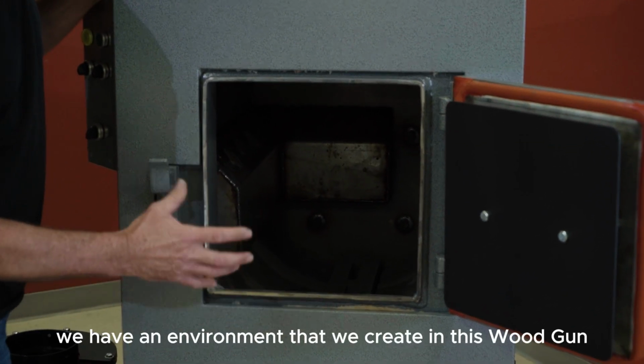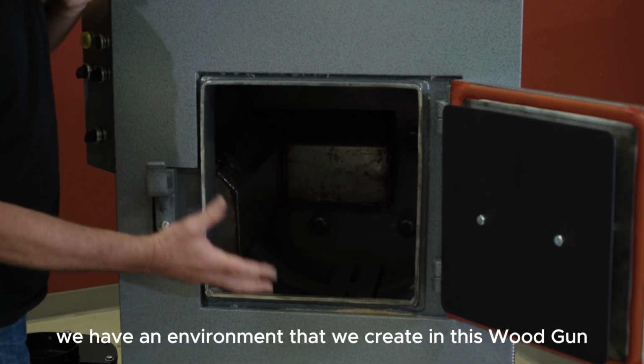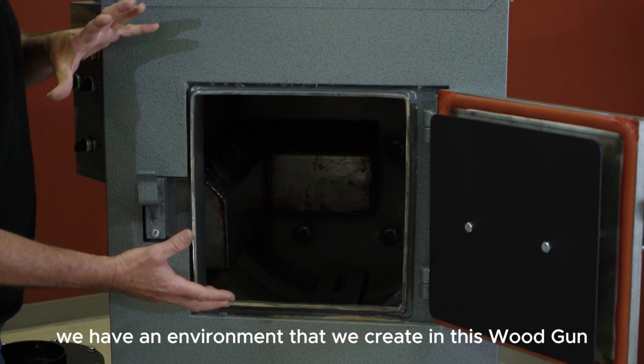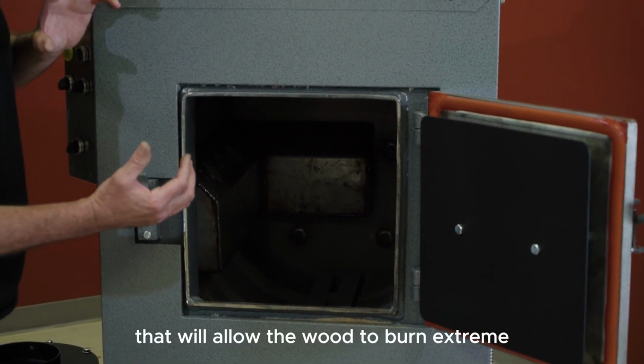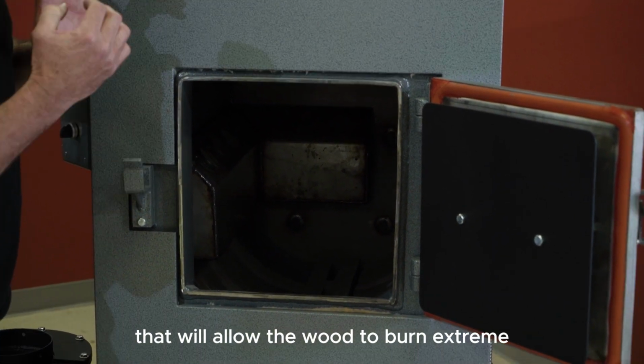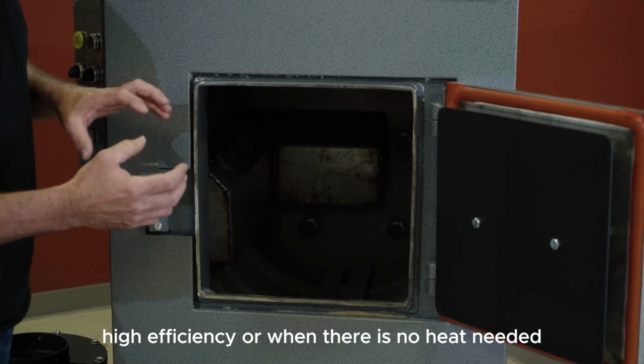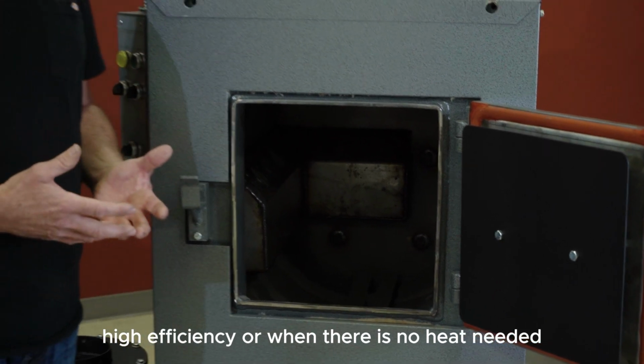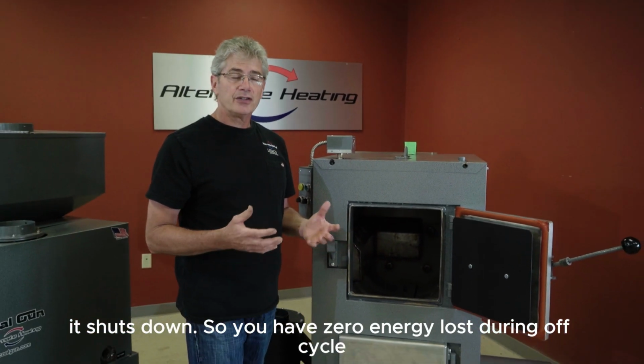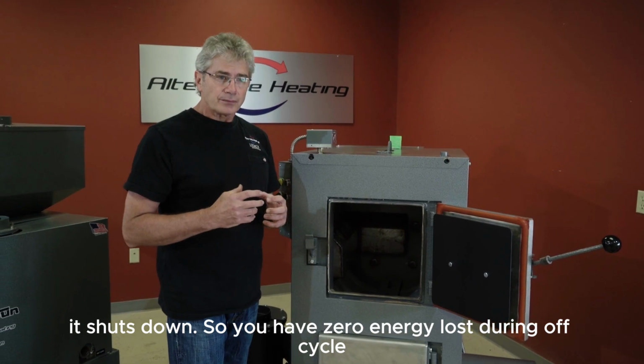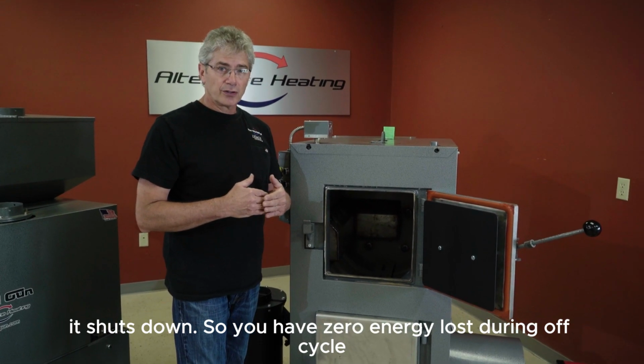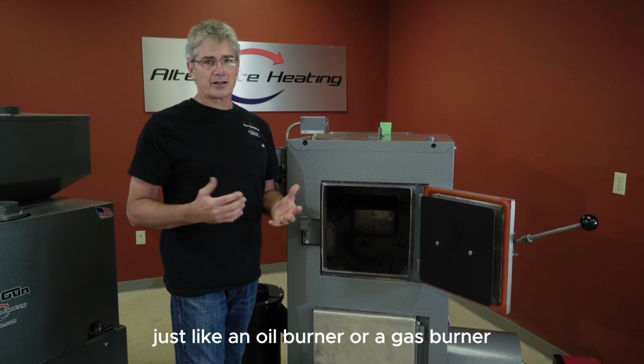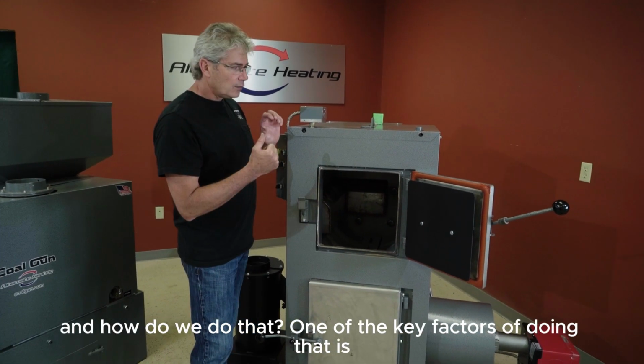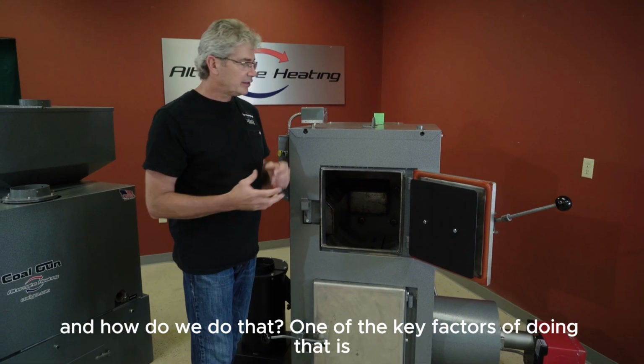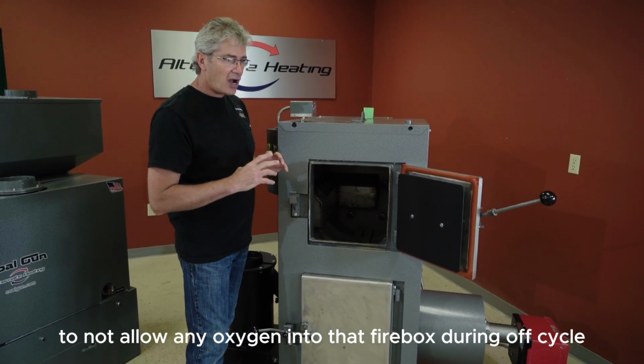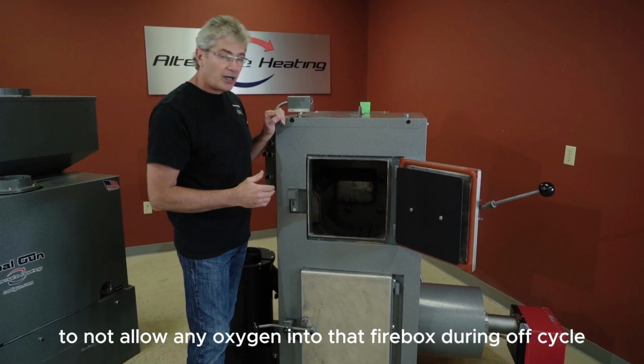So we have an environment that we create in this wood gun that will allow the wood to burn at extremely high efficiency, or when there is no heat needed, it shuts down. So you have zero energy loss during off cycle, just like an oil burner or a gas burner. And how do we do that? One of the key factors of doing that is to not allow any oxygen into that firebox during off cycle.